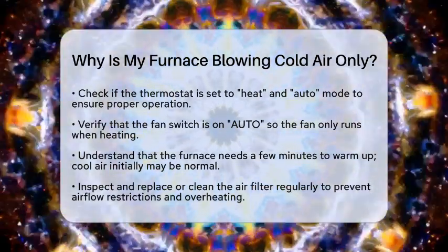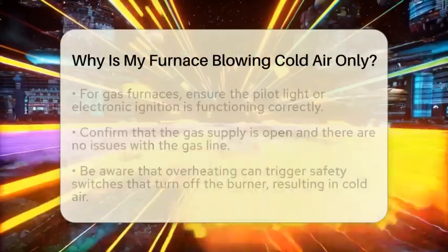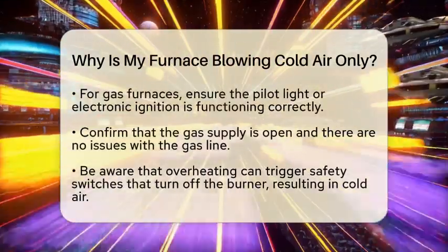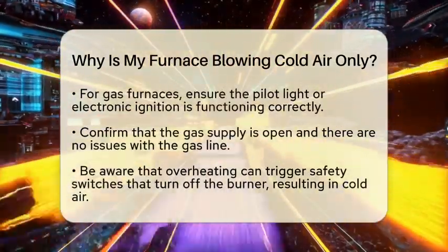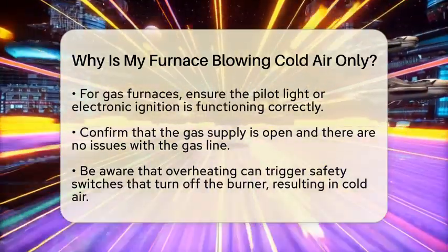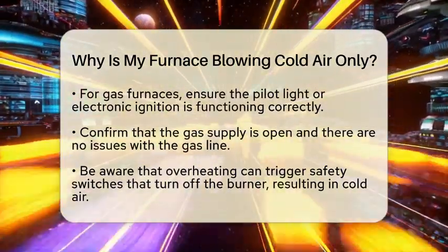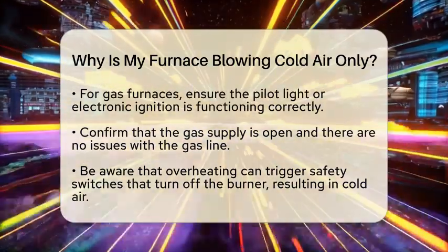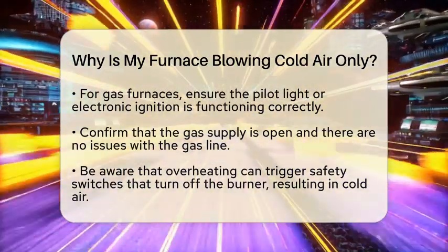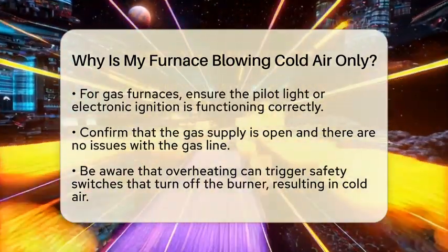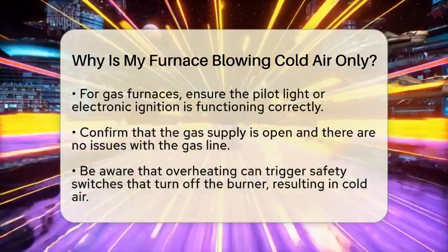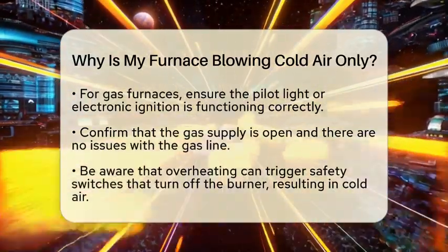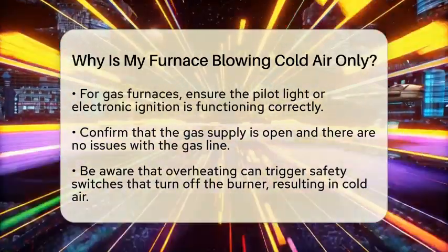A very common cause is a dirty or clogged air filter. When filters are full of dust and debris, airflow gets restricted. This can cause the furnace to overheat and trigger a safety switch that turns off the burner. When the burner stops, only cold air blows through the vents. Replacing or cleaning the filter every 1 to 3 months keeps airflow steady and prevents this issue.